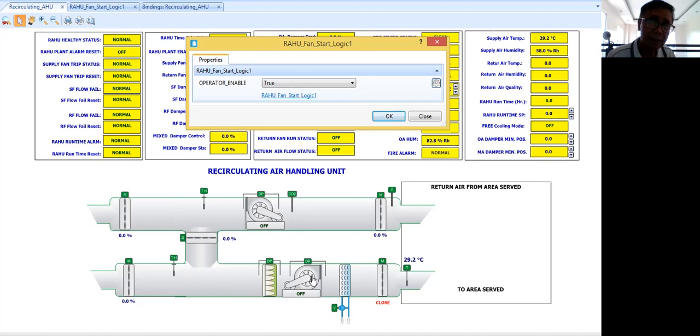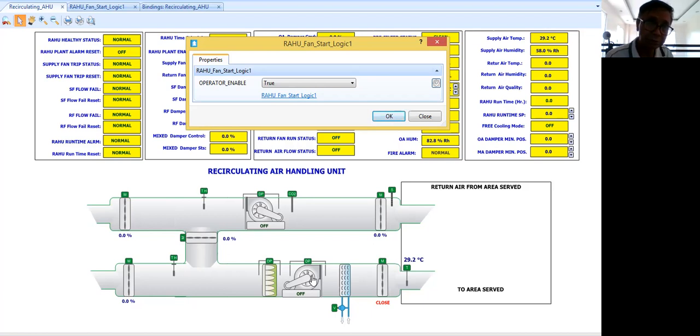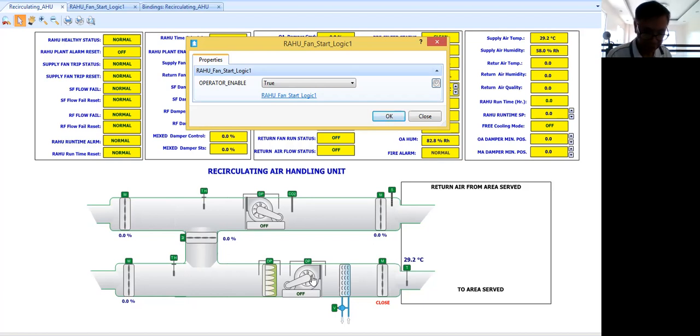So I want to create a gap between the starting. This is one practice to not put so much inrush current to your motor control. So that is the idea why I put some time delay.